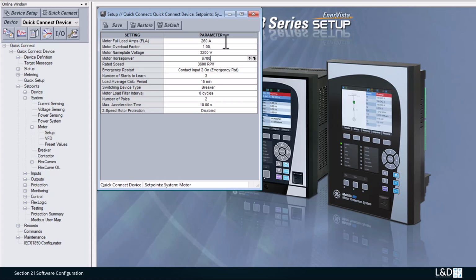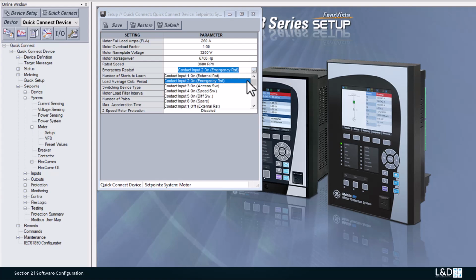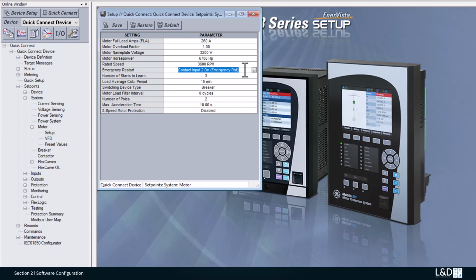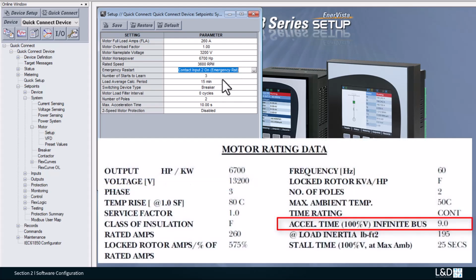The emergency restart, we left this to the default Contact Input 2 On, and this can be set to other contacts just in case you're using a different wiring. And for the acceleration time, we can set this to be 10 seconds. This is the default time, and this is just a little bit longer than the motor acceleration time in the datasheet.